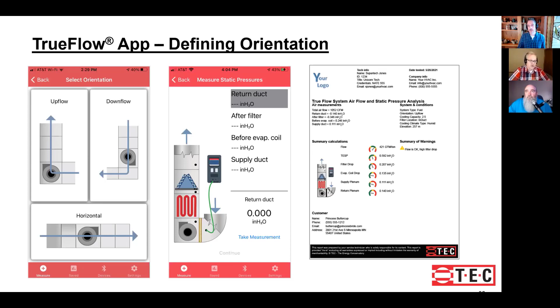The report gives you a dial indication of where you're at for the flow, total external static, filter drop, evaporator coil drop, and the supply and return plenum pressure. As we've said, that's to help you pinpoint what's wrong if there's a problem with the flow, or maybe the flow's okay but the pressures are off the chart because there are restrictions and you've got an ECM motor making up for the problems the system has.